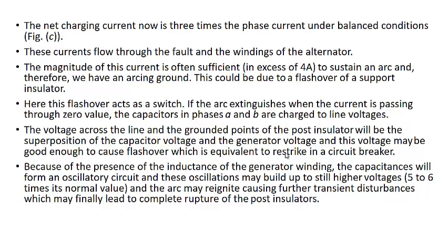Now in this case, since this acts as a switch, the arc has now extinguished. There is an open circuit. Now there is a voltage across the capacitor and a voltage across the source, that is, the generator. These two voltages add up and appear across this. We can say this acts as a switch or circuit breaker, where the arc has extinguished. Now this voltage is very high, and it will restrike again and cause the arc to be produced again. This makes the air ionized, and the arc will restrike again.